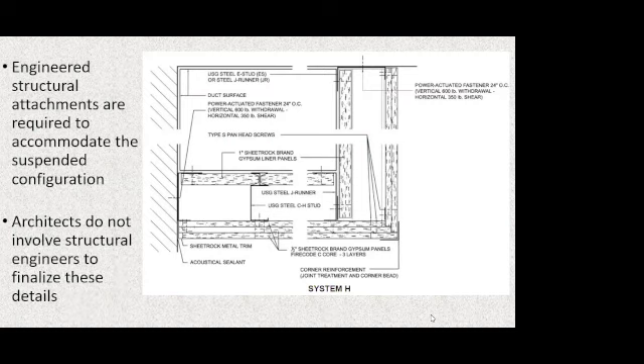And what you find from a competent structural engineer who's told to design that for the residual strength at 2,000 degrees is that it takes 600-pound pull-out and 350-pound shear. Somebody better check that, because your average drywall contractor is not going to install an anchoring system for lightweight steel framing that's 600-pound pull-out and 350-pound shear.